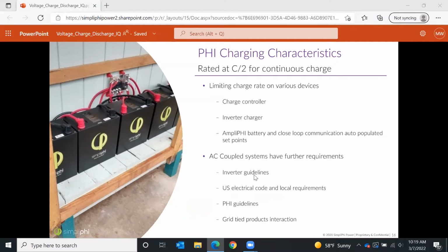Now, AC coupled systems - we've found they don't always communicate well between the battery-based inverter and the microinverters. So first, make sure you've got these checked: talk to both inverter manufacturers and confirm the firmware is up to date and the system is compatible. Secondly, make sure your AC PV array is sized properly so it doesn't overcharge the batteries. You don't want a giant AC coupled PV array with nowhere to send its energy but the batteries. The batteries get full, and the battery-based inverter tries to tell the microinverters to calm down and slow down charging, but they can't respond quick enough and end up overcharging the batteries.